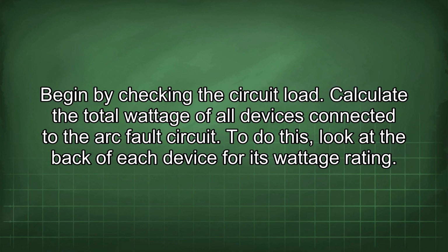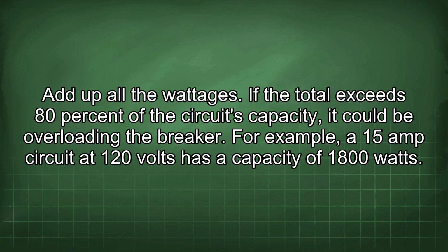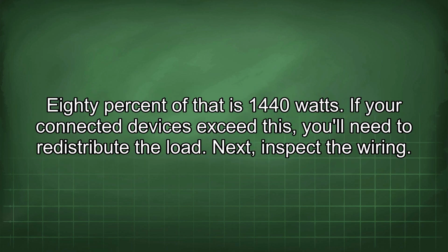Begin by checking the circuit load. Calculate the total wattage of all devices connected to the arc fault circuit. To do this, look at the back of each device for its wattage rating. Add up all the wattages. If the total exceeds 80% of the circuit's capacity, it could be overloading the breaker. For example, our 15 amp circuit at 120 volts has a capacity of 1800 watts. 80% of that is 1440 watts. If your connected devices exceed this, you'll need to redistribute the load.